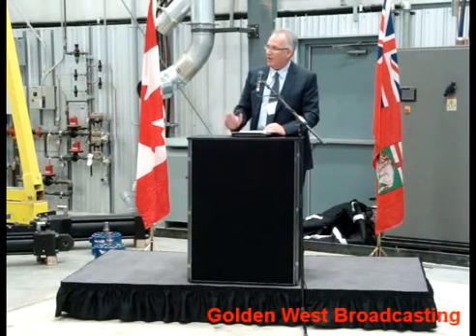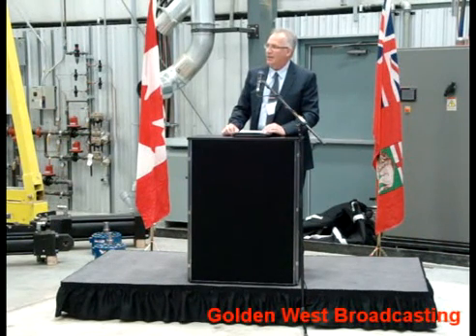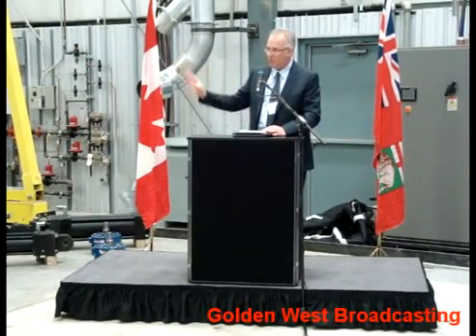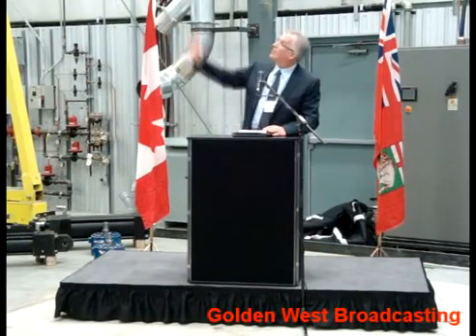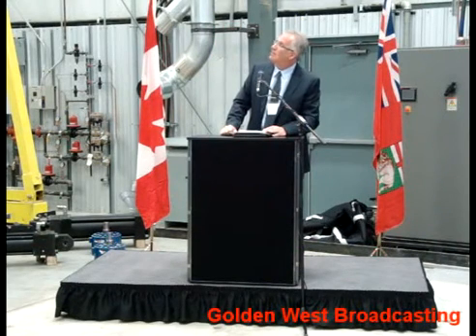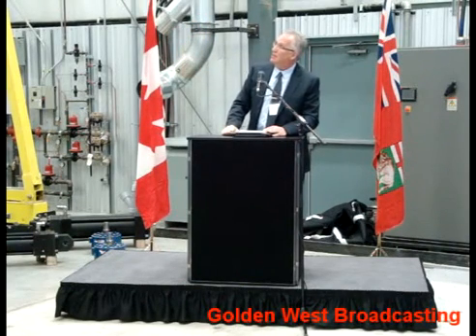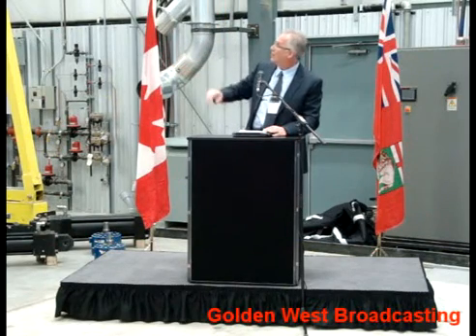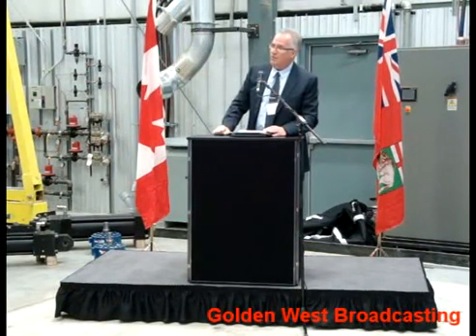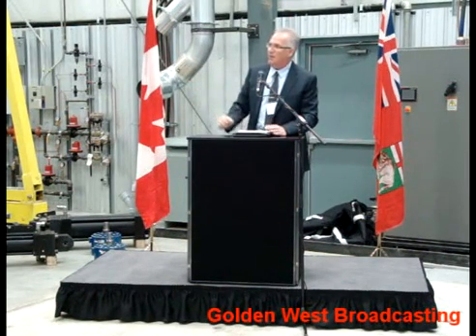The cooling heat, or the radiant heat that comes off the block of an engine, has to be dissipated. Now here's where we want control. If we want a repeatable test, the test parameters will say what temperature you want to run this test at. That's when you start having to add fans. If you look above us, you can see 5 fans up here. We've got another 2 fans in the corner, and this allows us to exhaust the air through the building and then pass it through a vent network in the front of the building and either mix it with the cooler air from the outside or keep recycling the hot air inside to get to whatever temperature we need.